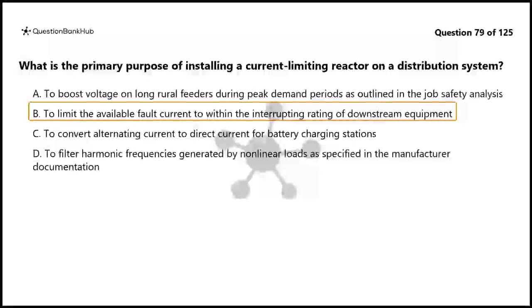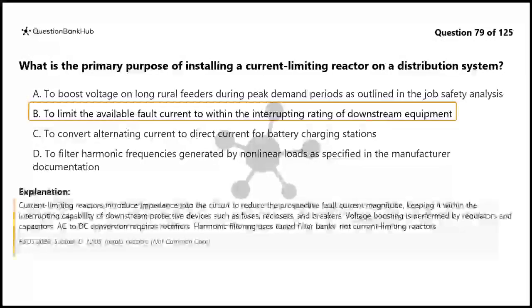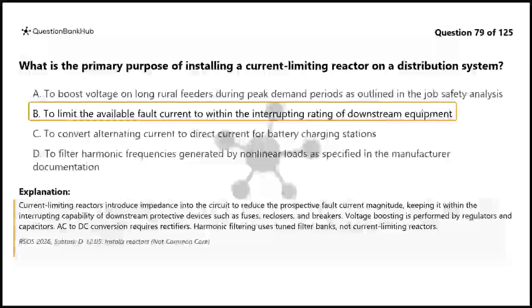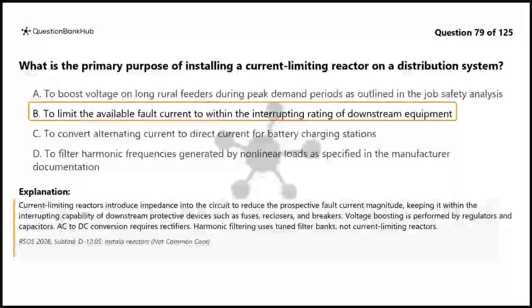The correct answer is B. Current-limiting reactors introduce impedance into the circuit to reduce the prospective fault current magnitude, keeping it within the interrupting capability of downstream protective devices such as fuses, reclosers, and breakers. Voltage boosting is performed by regulators and capacitors. AC to DC conversion requires rectifiers. Harmonic filtering uses tuned filter banks, not current-limiting reactors.